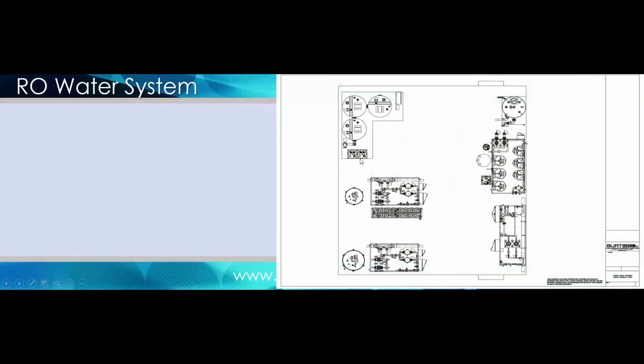These systems can get pretty big. This is a 60 GPM flow rate. This is your city water break tank. This is your pretreatment module. That's the size of your RO with your EDI. There's your EDI power panel there. Then you have your distribution. This is your DI racks essentially here.